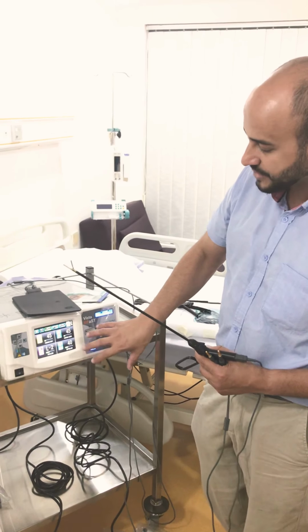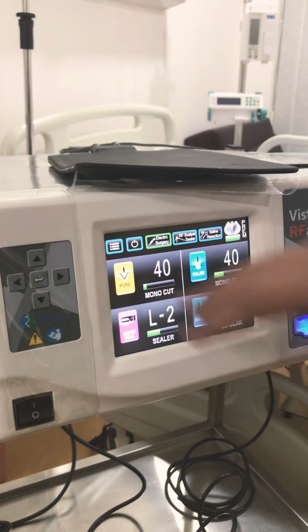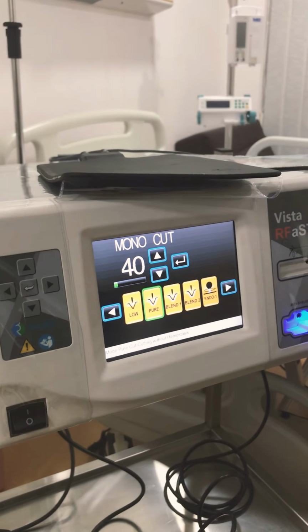If you want to go for electrosurgery, if you want to go for an RF, or if he's a urologist and he needs to go for a saline bipolar. This device as well can be programmed, okay? So you can either start by a single function from the beginning, or you can choose a program. For example, we are here putting a program for a laparoscopy under the name of Dr. Khalid. So all we just need to do is press on that and check load, and it will give you the same functions that you have programmed. And as well, you can edit functions and resave it again.